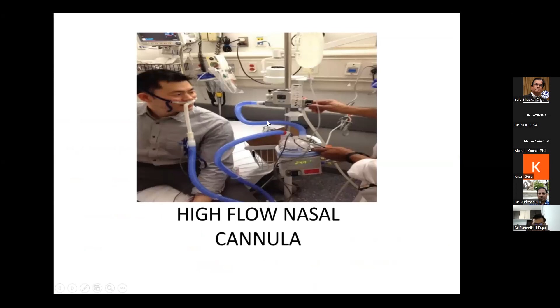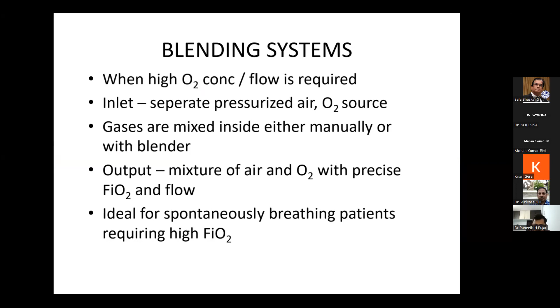Coming to blending systems, used when a high concentration of oxygen flow is required, they mainly consist of an inlet for pressurized air and an oxygen source. Here the gases are mixed either manually or with the help of a blender. As output we have a mixture of air and oxygen with precise FiO2 and flow. The blending system is mainly used for spontaneously breathing patients requiring high FiO2.